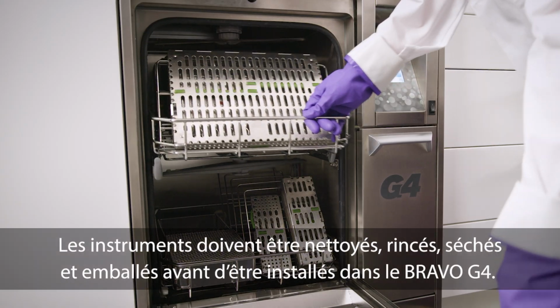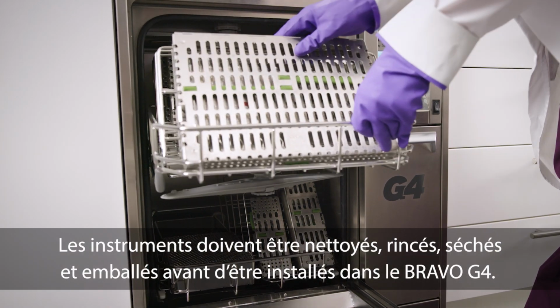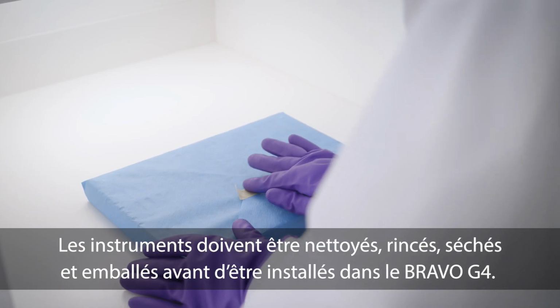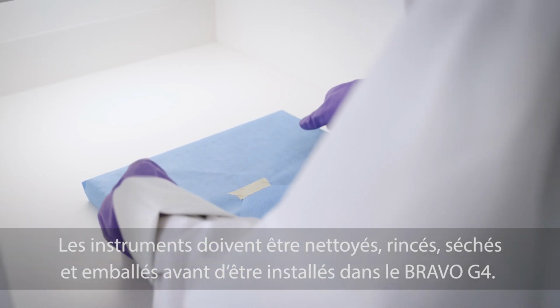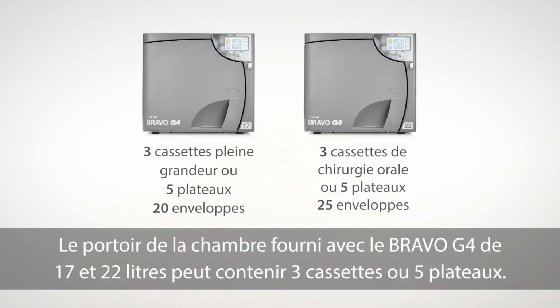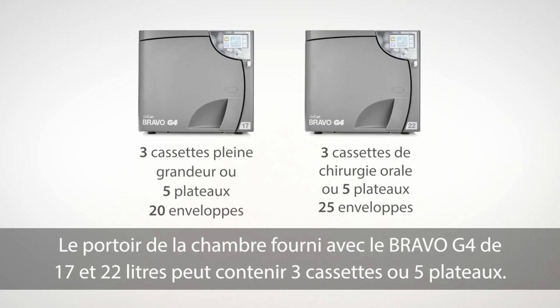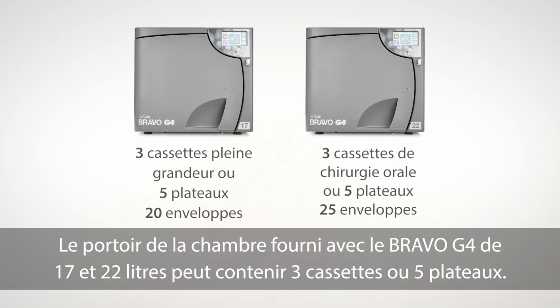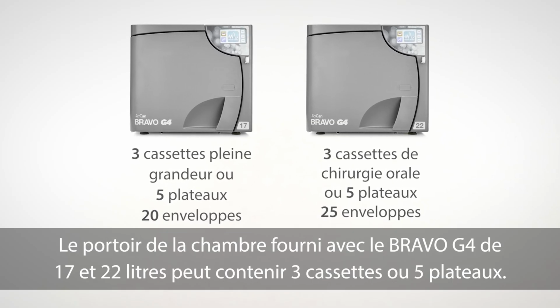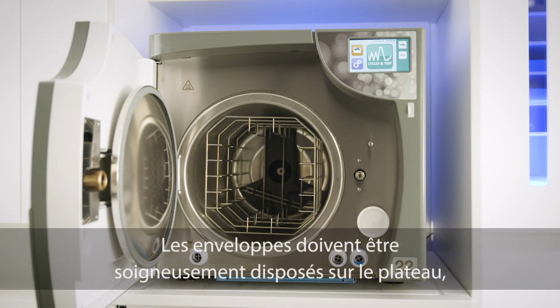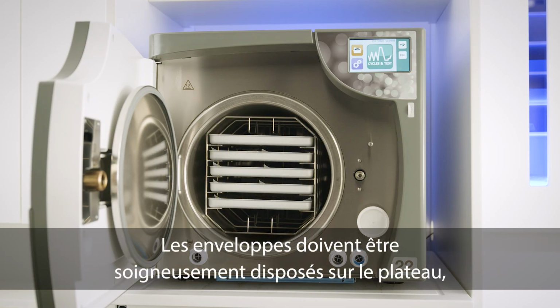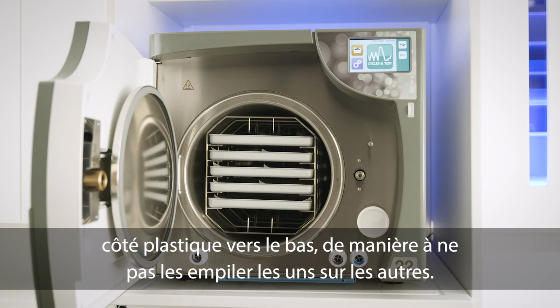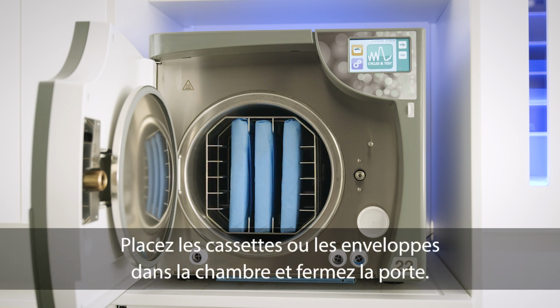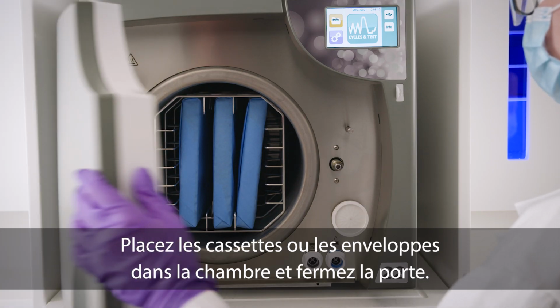Sterilizing instruments. Instruments must be cleaned, rinsed, dried, and wrapped before being placed in the Bravo G4. The chamber rack included with the 17-liter and 22-liter Bravo G4 will hold 3 cassettes or 5 trays. Pouches should be carefully arranged on the tray, plastic side down, and in such a way that they do not overlap. Place the cassettes or pouches in the chamber and close the door.